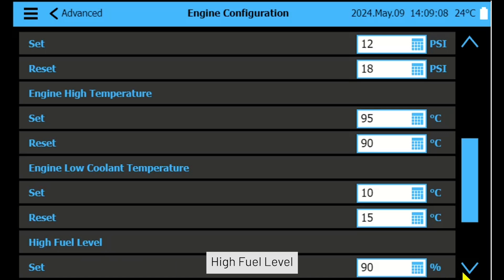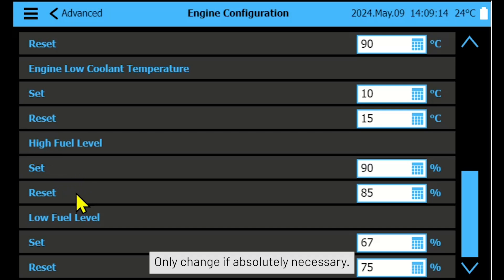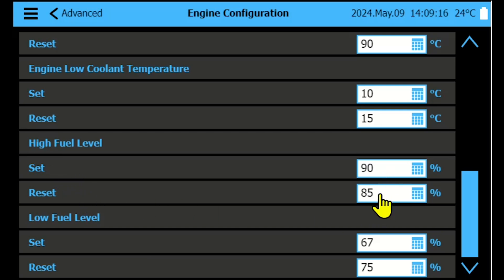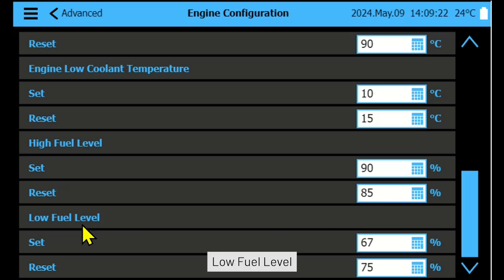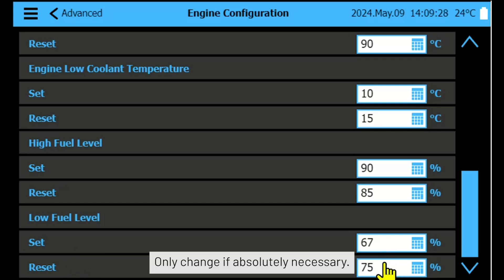High fuel level: set and reset points are factory set to 90% and 85% — only change if absolutely necessary. Low fuel level: set and reset points are factory set to 67% and 75% — only change if absolutely necessary.